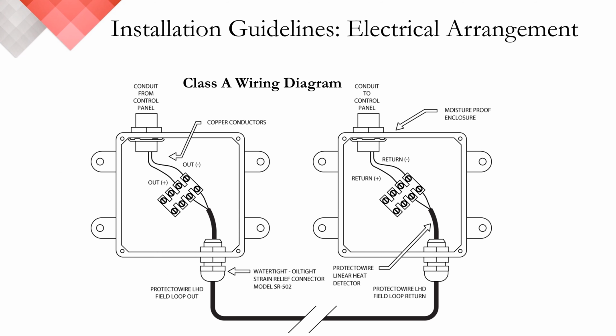And similar to our Class B, here we're showing the installation using Class A or Style D wiring. As you'll notice, the illustration is very similar to our Class B wiring diagram. Primary exception is rather than ending with the end-of-line resistor, we're continuing the circuit, and the end of the zone is transitioning back to the appropriate feed cable, which is then routed back to the control panel or interface module.